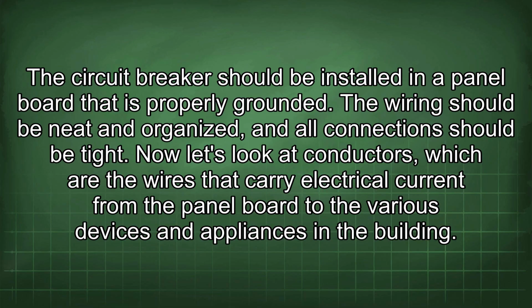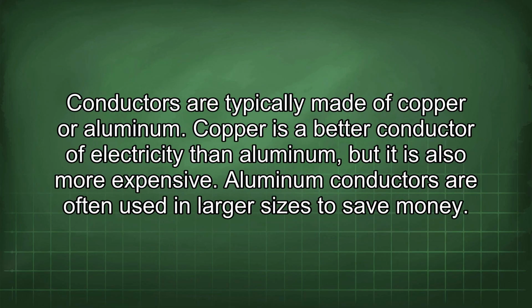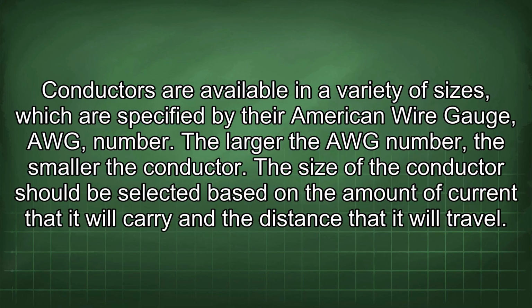Now let's look at conductors, which are the wires that carry electrical current from the panel board to the various devices and appliances in the building. Conductors are typically made of copper or aluminum. Copper is a better conductor of electricity than aluminum, but it is also more expensive. Aluminum conductors are often used in larger sizes to save money. Conductors are available in a variety of sizes, which are specified by their American wire gauge, AWG, number.